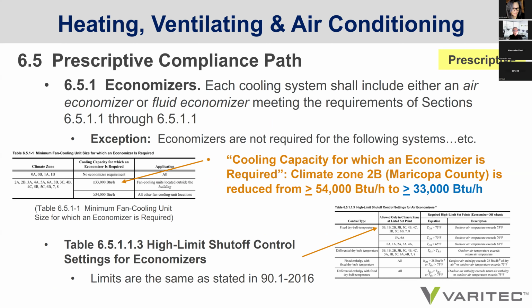Under the prescriptive section, there's language now on economizers. Each cooling system shall include either an air economizer or fluid economizer, meeting the requirements of the designated sections. Economizers are not required for the following systems. But if you look at the cooling capacity value for economizer usage, it has been reduced from 54,000 BTUs to units that are at 33,000 BTUs or greater. So economizer requirements for smaller units is now embedded in the language.